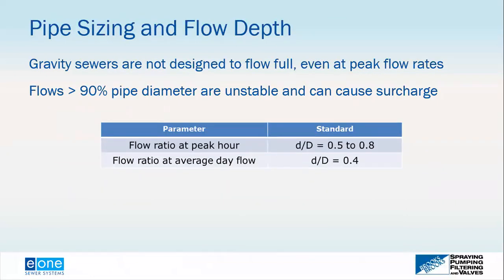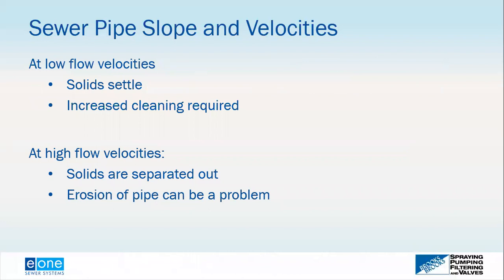For gravity sewer system design, the pipe slope is set to maintain proper velocities. At low velocities, solids settle out, increasing cleaning requirements and causing hydrogen sulfide generation — that rotten egg odor you smell from manholes. At high velocities, wastewater moves faster than solids, still causing separation, and the higher flow forces can cause erosion and wear on the pipe or create hydraulic concerns at bends. The standard design targets a minimum velocity of 0.6 meters per second and a maximum velocity of 3.0 meters per second.